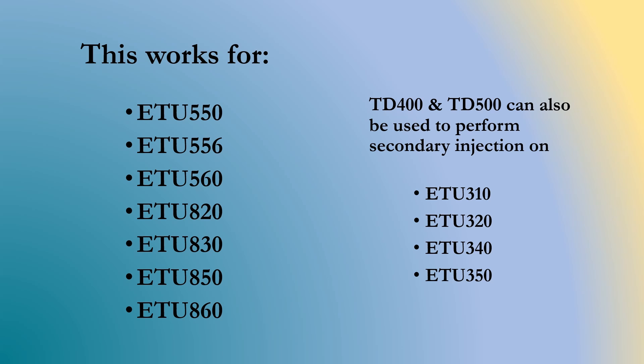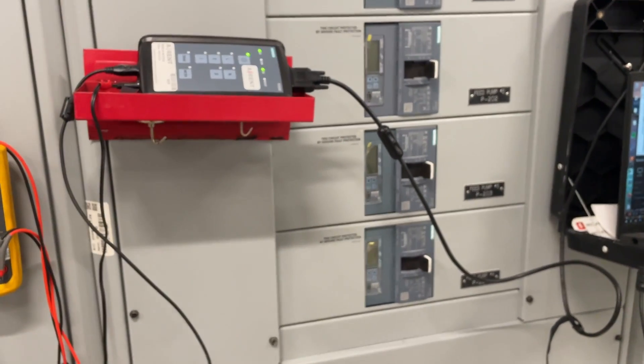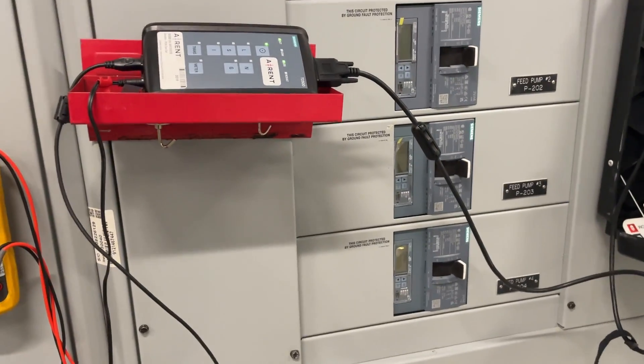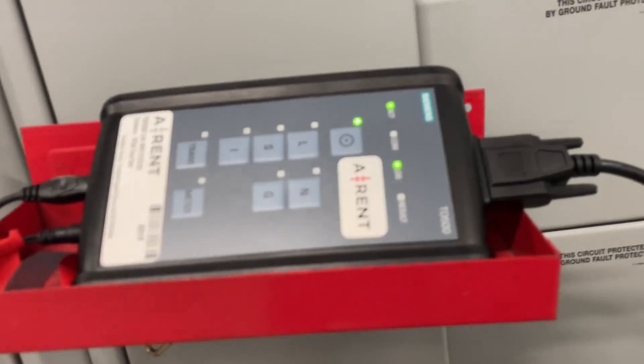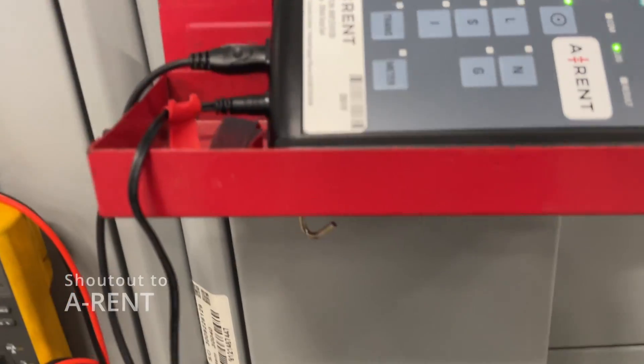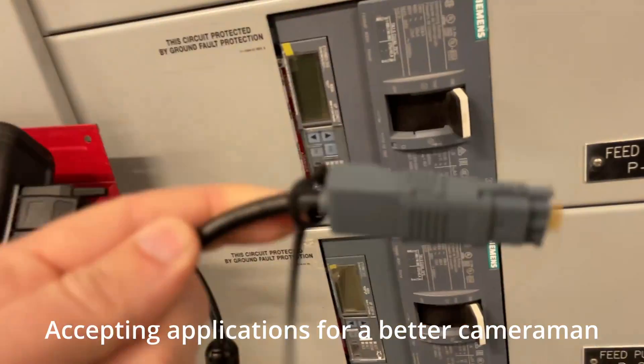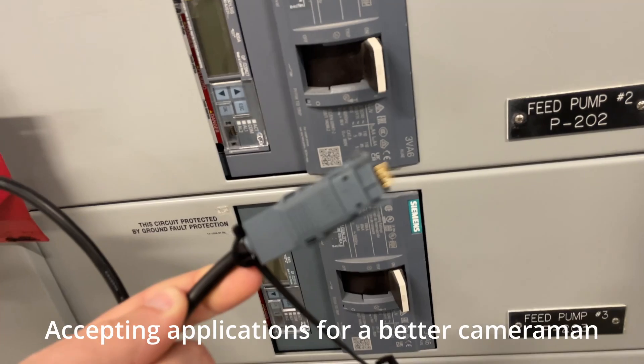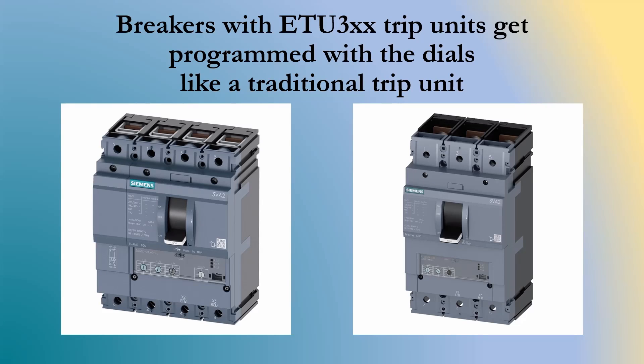Both of which can connect to your laptop using a USB cable. So you'll run the Sentron Powerconfig software. The setup you'll need: obviously we need to provide power from the little wall adapter to the TD-400 or TD-500. It needs to be connected to your laptop over USB and then obviously the program and test cable will go between the TD-400 or TD-500 and your trip unit.